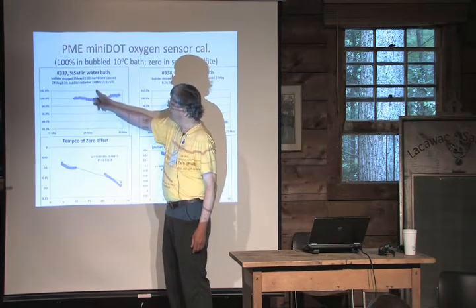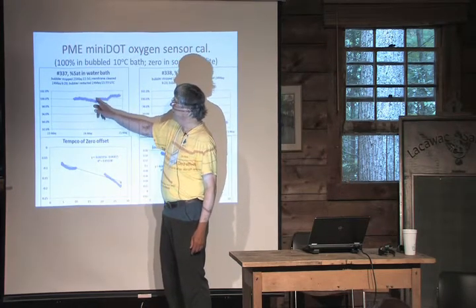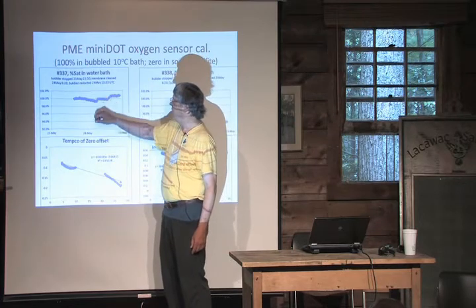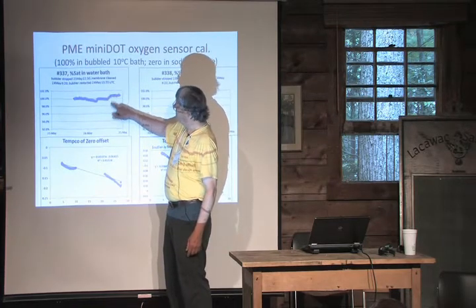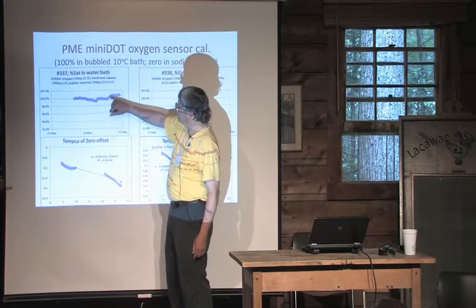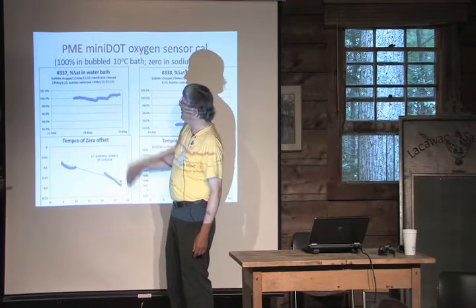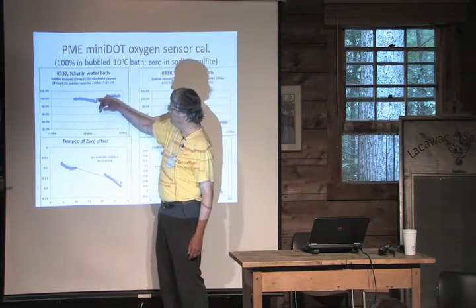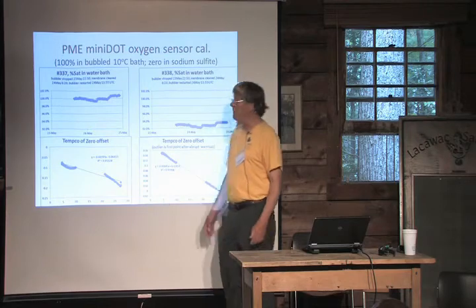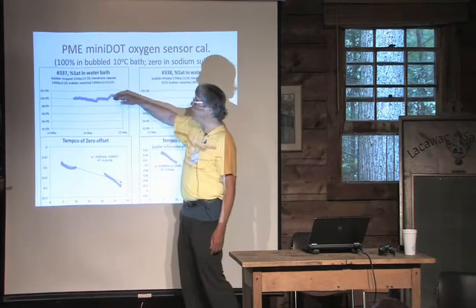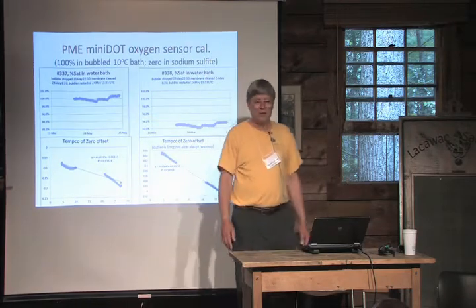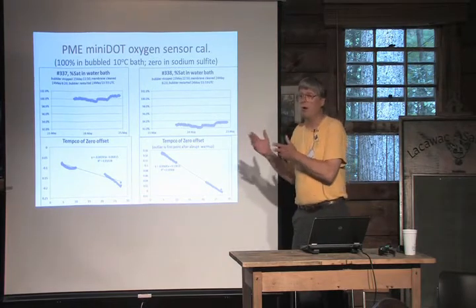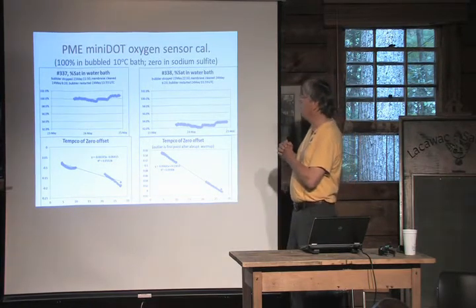Actually, right here, I cleaned them. I took the electrode out, cleaned the surface off as recommended, put it back in, and this was without the bubbler, and then back up here with the bubbler on. So it may be the difference between this downslope and this horizontal slope is the effect of the biofilm, but it's a very small percentage. It's a fraction of 1%. So it showed us in this case that we didn't have to worry about biofouling during that deployment.